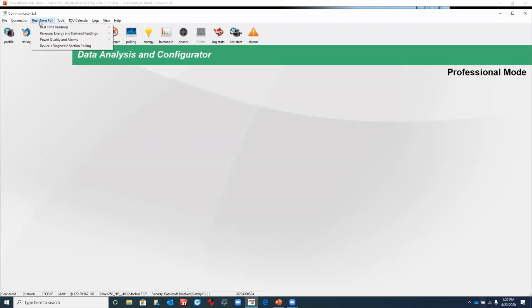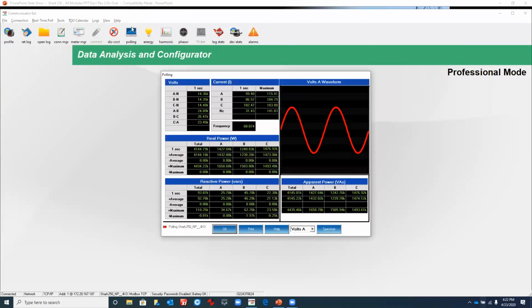So I'll look at the real-time poll, and we'll look at the real-time readings. So the real-time readings, we'll move over to instantaneous polling. What you see are the real-time meters updating instantaneously, on what we call real-time. And what you can see is the voltage on the left side, VAN, VBN, VCN, all voltage A to neutral, B to neutral, C to neutral, phase-to-phase voltage, A to B, B to C, C to A, and your instantaneous currents, IA, IB, IC, and the neutral current.